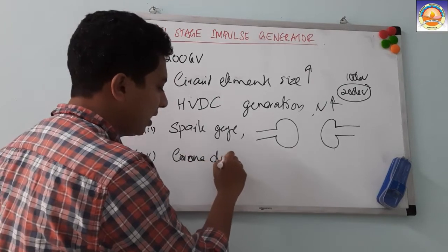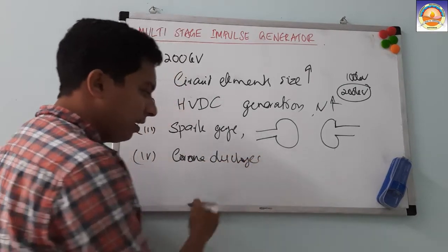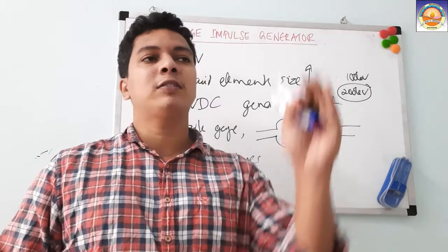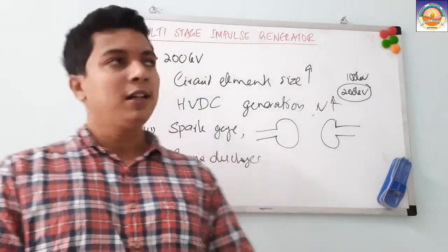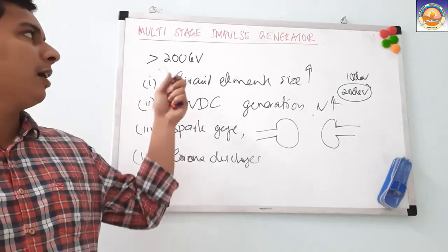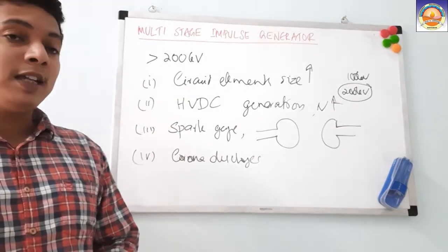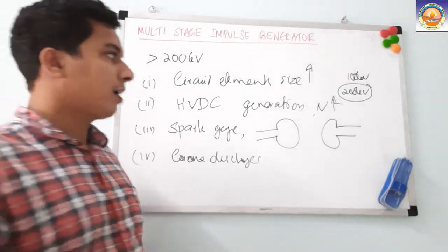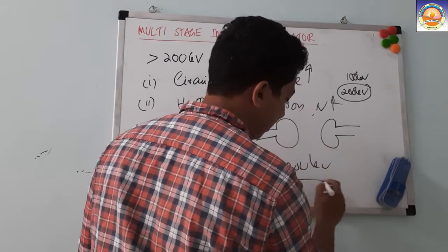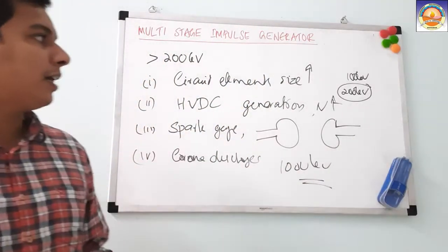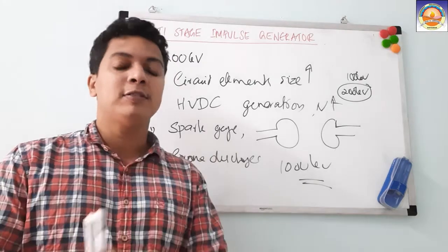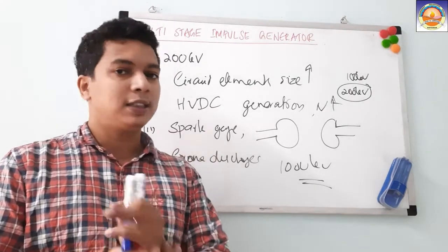Another problem is that corona discharges can happen in the leads when each component has such a high voltage rating. Due to all these problems, we have to think about a multi-impulse generator, because for lightning impulse we are talking about 1000–1400 kV, and to generate that we cannot use a single-stage impulse generator.